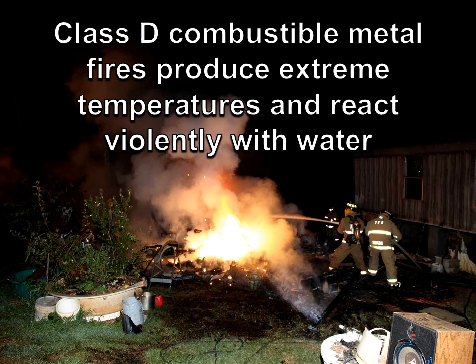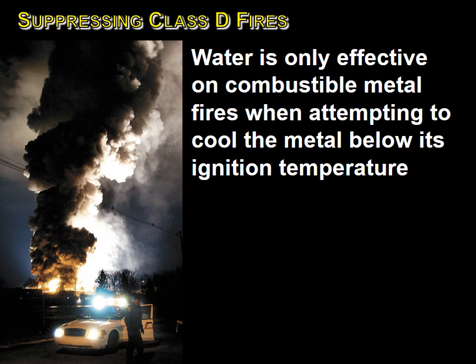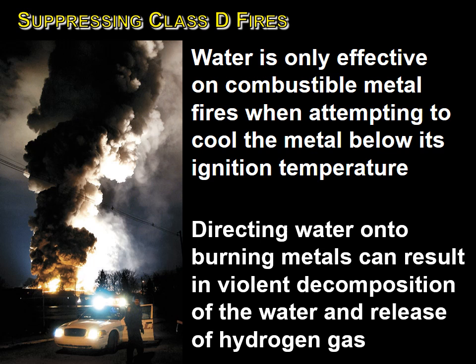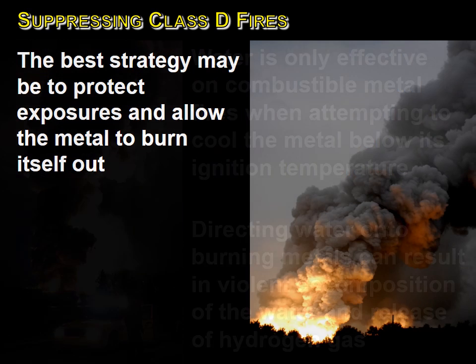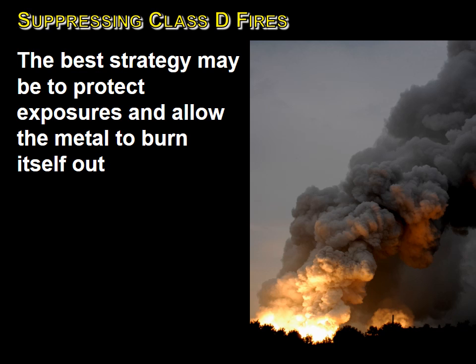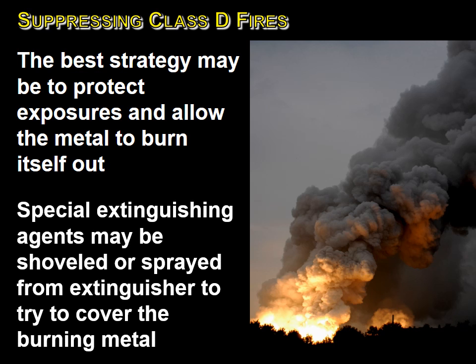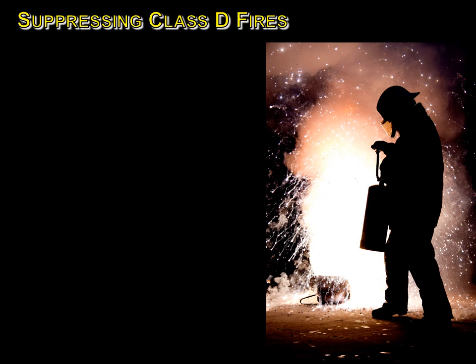Class D combustible metal fires can produce extreme temperatures. Water is only effective on combustible metal fires when attempting to cool the metal below its ignition temperature. Directing water onto the burning materials can result in a violent decomposition of the water and release of gas. The best strategy may be to protect exposures and allow the metal to burn itself out. Special extinguishing agents may be shoveled or sprayed from an extinguisher to try to cover the burning metal. An ash layer may cover the burning material and give the impression the fire is out, but there may be an extended period before the metal cools to safe levels. Combustible metal fires may be greater than 2,000 degrees Fahrenheit even after they appear to be out.